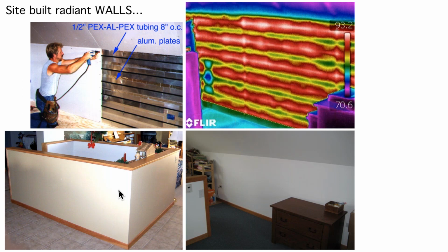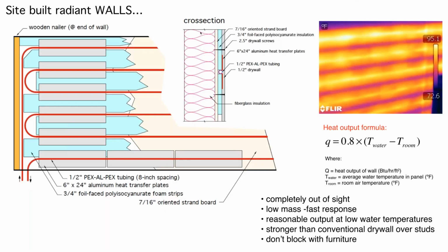Again, this is running at relatively low surface temperatures. You can see in the thermal image, the highest temperature here is only 93 degrees Fahrenheit. So this wall feels just slightly warm to the touch, but there's enough surface area there to heat that entire space. So floors, walls, and ceilings can all be done with radiant panels and all be done with low water temperatures that really allow that heat pump to perform well. Again, the construction of the wall, same system as the ceiling, another thermal image, and then the output.